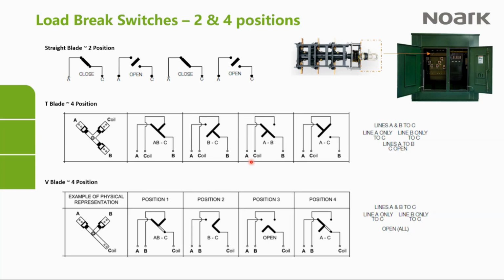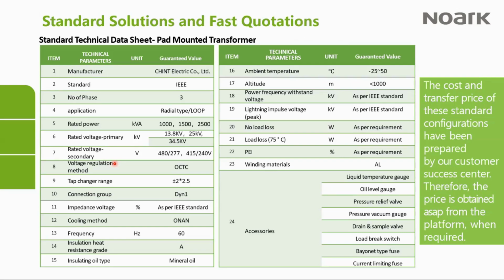So if you have, for example, an off circuit tap changer, and you want to change the position, then you have to put the load break switch at this position here, so that you have completely de-energized the transformer. Then you can go ahead and change the tap position, because there is already a voltage fluctuation, and you want to compensate for that so that you still get the right voltage at the secondary side. So that's how we use the load break switches, together with the other components that you have in the transformer.